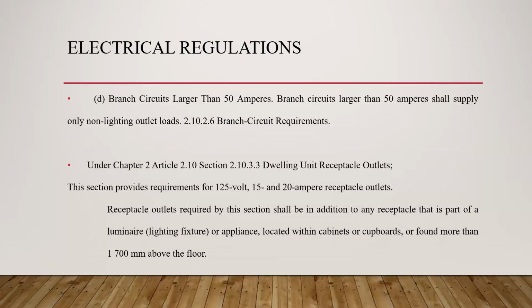And last, letter D, a circuit larger than 50 amperes shall supply only non-lighting outlet loads under 2.10.2.6 branch circuit requirements.